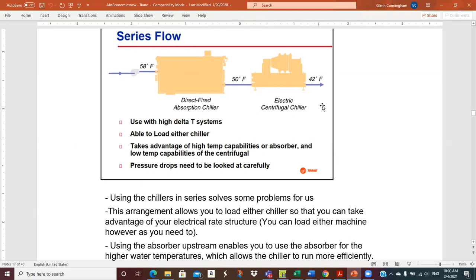Now, we can put bypasses around these things, which is probably what the designer would want to do if they didn't turn out to be too expensive. You would have to evaluate that versus the extra pumping energy. But for example, if you're using the absorber, when you come out at 50 or whatever degrees, if you're done cooling the water, then you could have automatic valves where you shut off the flow here and you simply bypass around the chiller and you don't incur this. It's probably 15 to 20 to 25 feet of head loss across this evaporator coil, and there would be not very much at all through the bypass. There would be some through the extra piping and valves, but maybe 4 or 5 feet, something like that. So there would be a large reduction in the pressure loss that you would see as compared to if you piped it up like this.